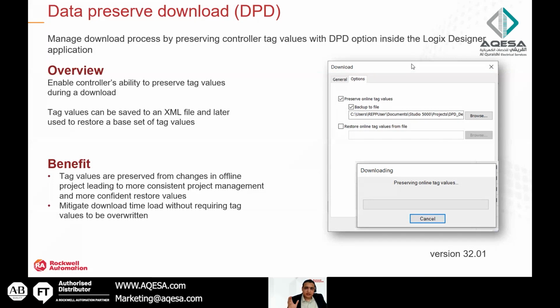Data preserve download. Before, you needed to download - let's say you take a backup this month from your controller, and you download it after 3 or 4 months or a year. If you have a flow totalizer, or some calculations in the tags, and you need to download after a year, you'd get the information that was there a year ago. But now you can preserve download, downloading only the ladder, not the tag database or tag values. This saves time, saves memory, and keeps the latest information on your CPU.